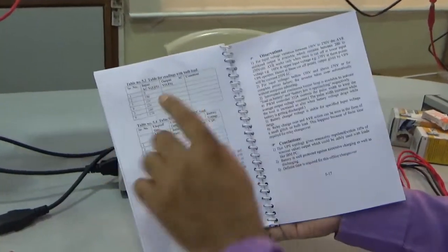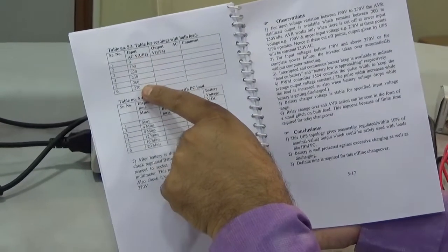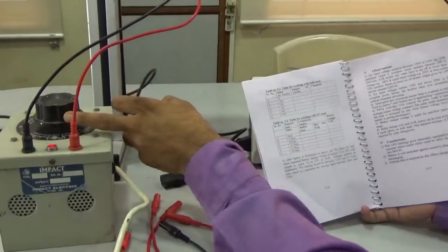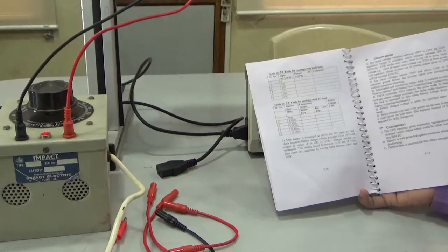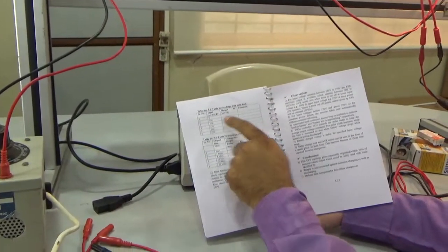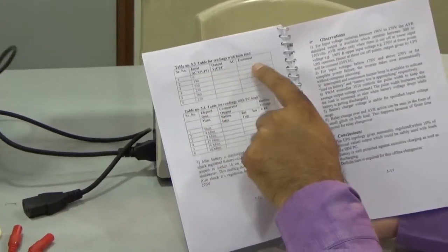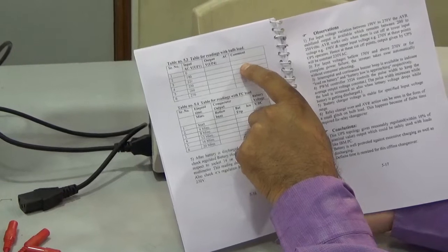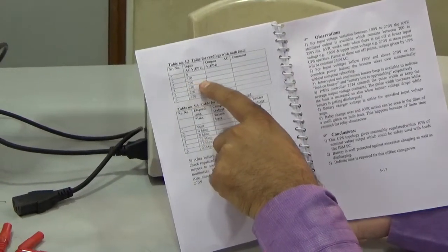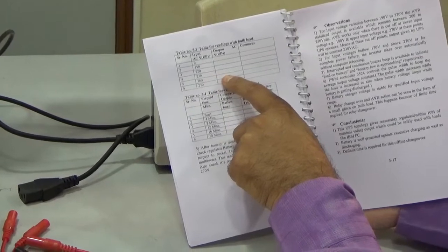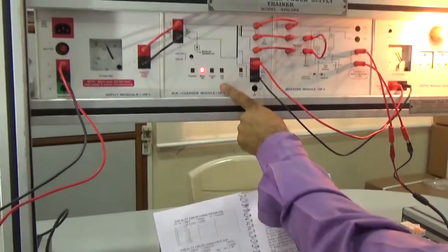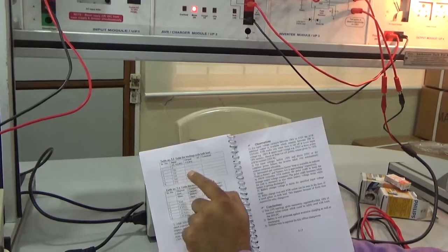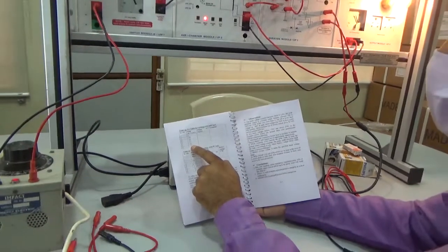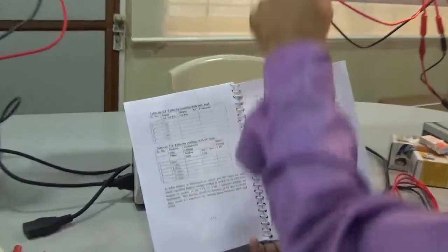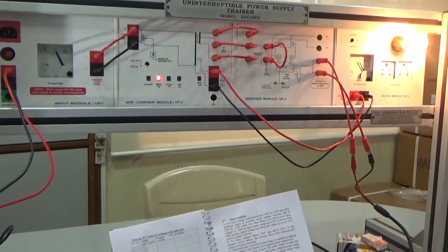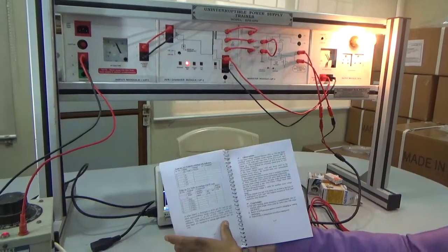Here is the observation table. Here are the different input voltages that we have to adjust using the dimmer. Output on UPS we have to measure at 190 volt or below. Our UPS will be on and mains will be off. At 220, 230, 260 our mains will be on and UPS will be off. At 270, at over voltage, mains will be off and UPS will be on. That we have studied in chapter 5A, study of changeover logic.